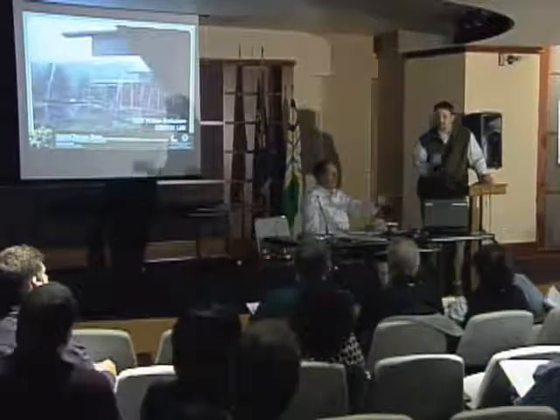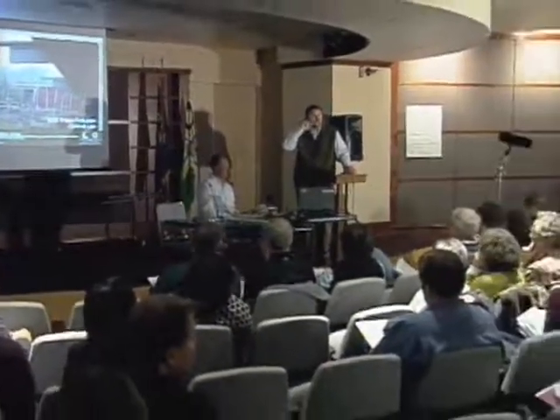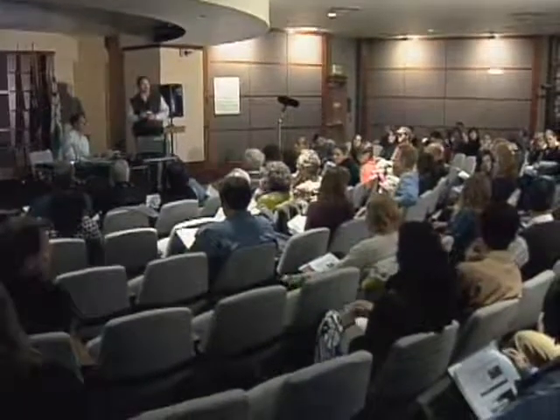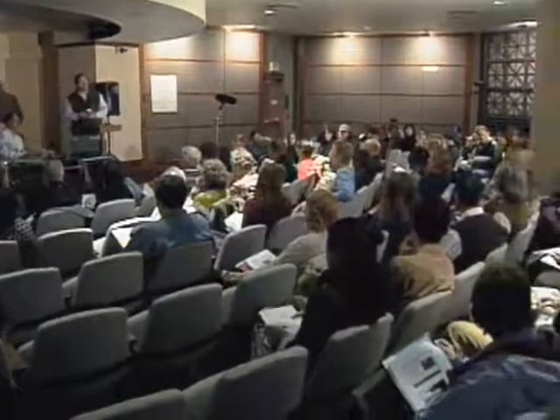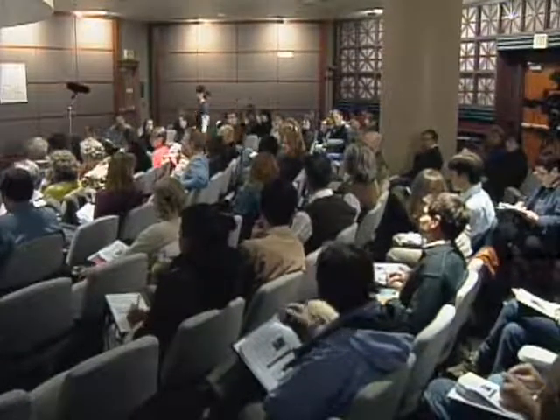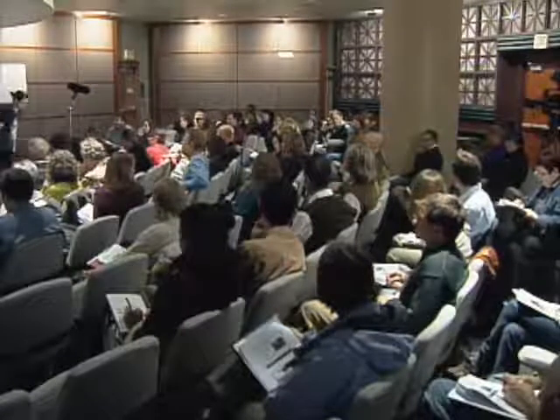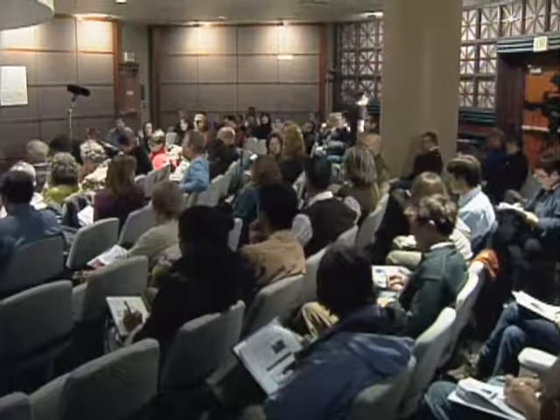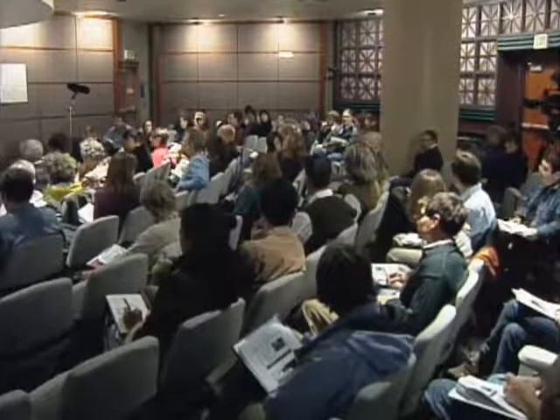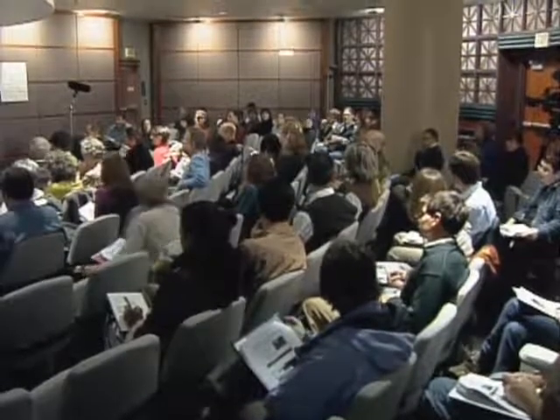Sometimes if you go to our site, and it's raining, I think that's actually a plumbing code issue, and there is a building code interpretation out there regarding gutters and not gutters in the plumbing code. And as I recall, it says basically, okay, you can do something because there's this rain drift product out there that triggered this, but you have to deal with it essentially the same way you would if you had the gutters and downspouts. That is, the gutter collects the water, it brings it down, and then it keeps it away from the building foundation, and then it sends it somewhere. So you have to design where the water is shed to protect the building foundation and direct that water in an appropriate way.